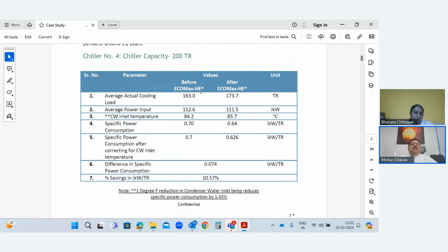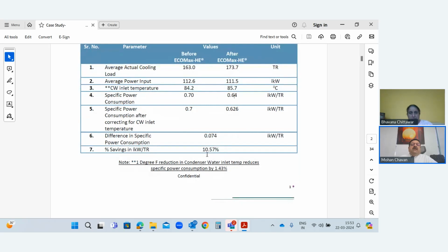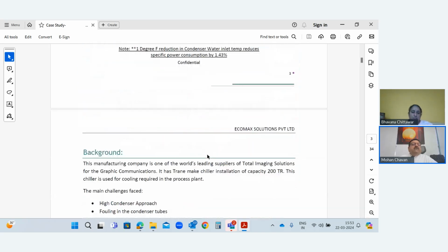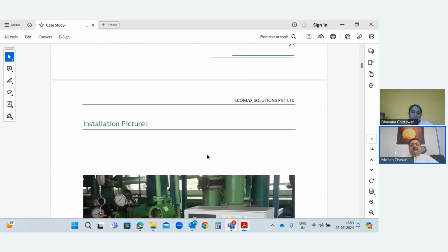So this was the actual cooling load before, that is 163 TR. After was 173 TR. Power input was 112.6 kilowatt, and after was 111.5 kilowatt. And specific power consumption was 0.7 to 0.64, which is now corrected to CW inlet, because CW inlet before was 84.2 and after was 85.7. This is Fahrenheit actually, this is not correct. So you can see a clear difference of almost 10.57% in the kW per TR by using the automatic tube cleaning system. This is installed on a Trane chiller.